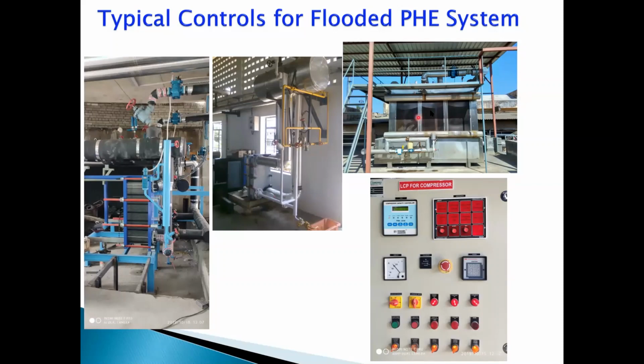This is another example of a plate type chiller system. In this, you have the plates and you have the liquid feed system. This one is with the back pressure regulation. This is a typical control panel for smaller chiller applications where you can do full automation using a simple controller and a small panel. For this type of chillers, you don't need very specialized big panels. You can make a fully automatic plant using these small components.